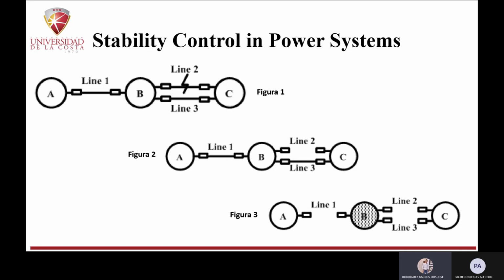The overview of current stability control in power system. The existing stability control devices are distributed in some vulnerable sites. The sites are chosen by pure offline computation based on stability analysis. They are independent and only serve the local site. Then a strategy table for stability control under potential contingencies is worked out by offline simulation. Therefore, the operation limit is conservative in the current state, the local control device and system control center.